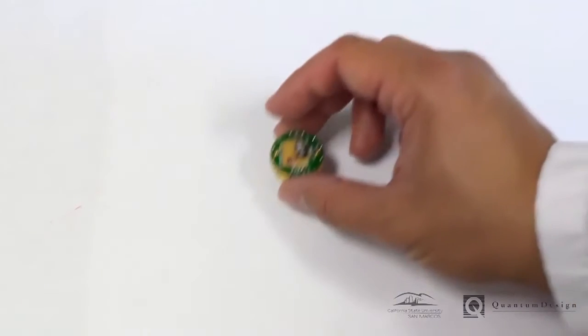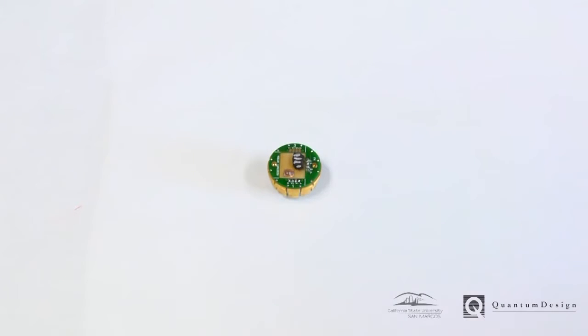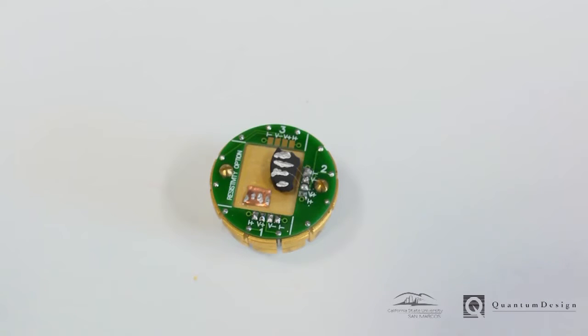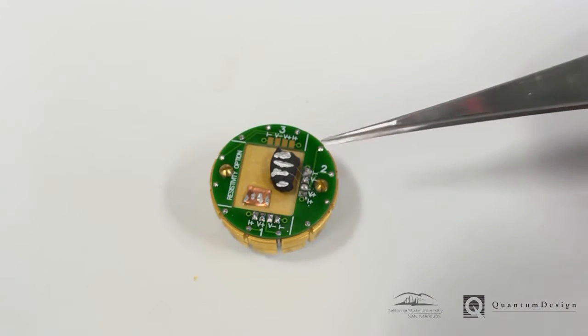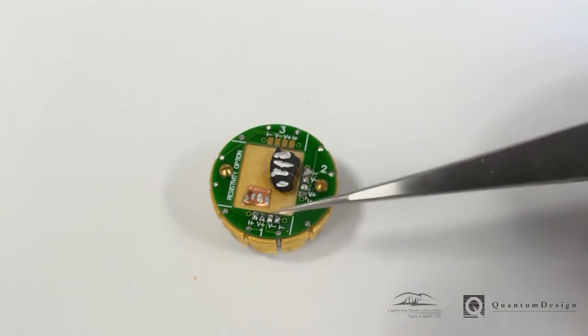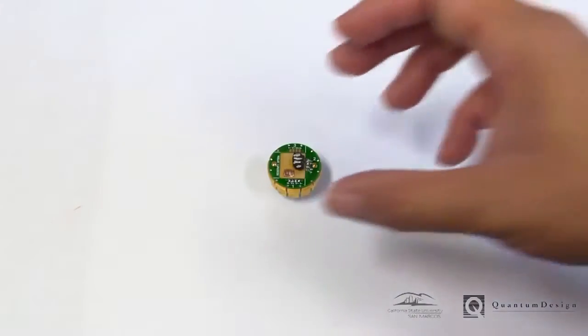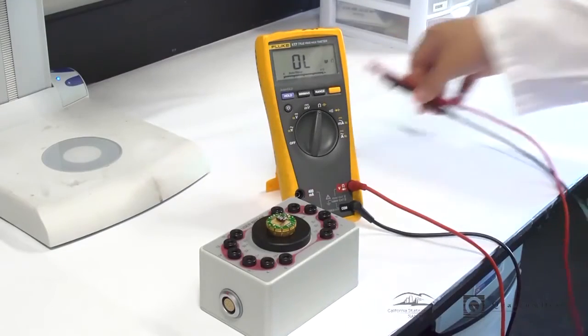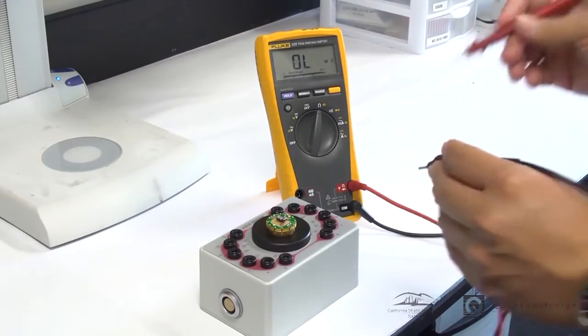Two channels are available for simultaneous measurement, and samples can be wired in either two-wire or four-wire measurement configurations. You may solder directly to the puck pads. Here we have a sample of YBCO superconductor and a sample of copper foil connected by platinum wires and silver paint. It's a good idea to check your contacts before you load the puck into the VersaLab.